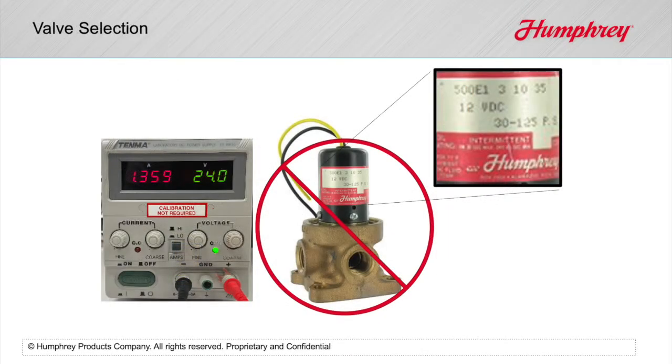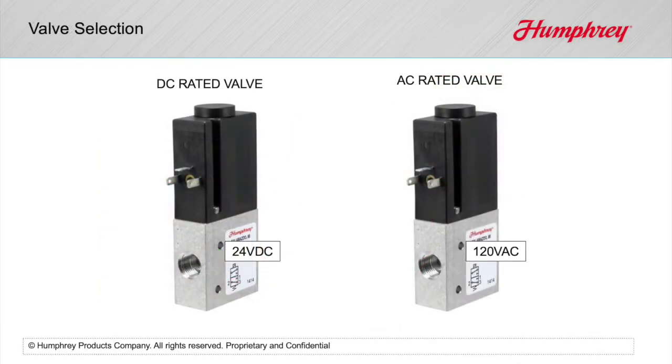You want to make sure you control the solenoid valve with the correct signal. Do not apply 24 VDC to a 12 VDC valve. Do not use AC voltage for a DC voltage rated valve.